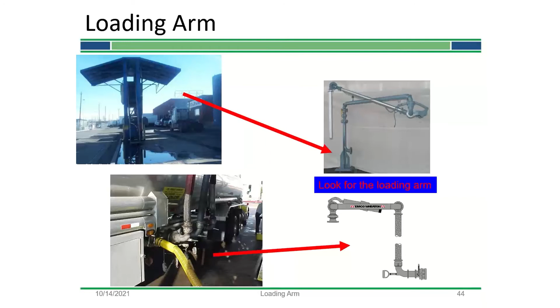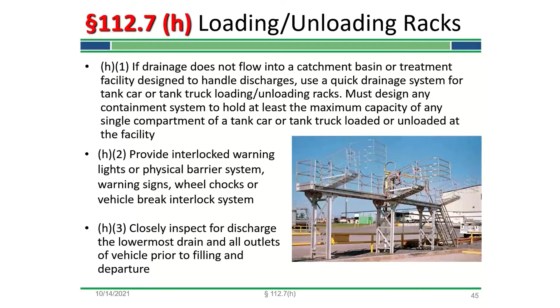So for loading unloading racks, if drainage doesn't flow into a catchment basin or a treatment facility designed to handle discharges, you have to use a quick drainage system, or you also must design any containment system to hold at least the maximum capacity of any single compartment of a tank car or tank truck loaded or unloaded at the facility. So no freeboard requirement. You'll also need to make sure that your tank truck doesn't accidentally depart before disconnecting by providing interlocked warning lights or physical barrier systems, warning signs, wheel chocks, or a vehicle brake interlock system. And don't forget to inspect the lowermost drain and all outlets before filling and departure.